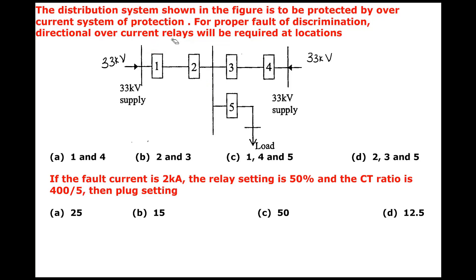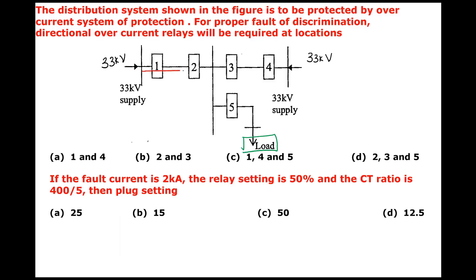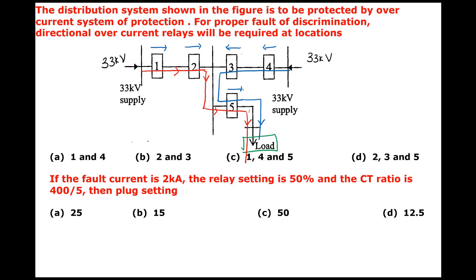When the system is healthy and load is present, the currents will flow from the supply source to the load in this direction — that is the direction of current flow under healthy conditions. From the other 33 kV feeder, currents will also flow to the load in this direction. These are the healthy current directions for all the relays.